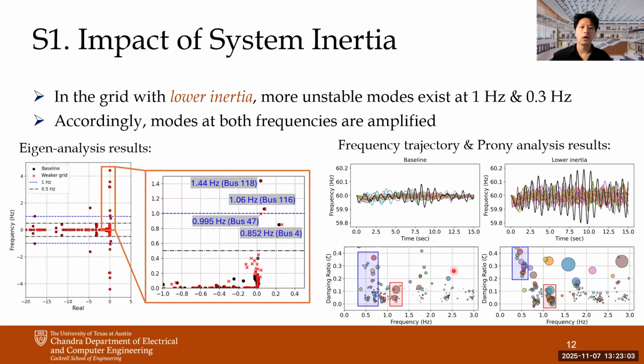Then we move to how the various factors can affect this kind of oscillation. And the first factor will be the system inertia. Basically, if the system has a lower inertia, there will be larger oscillations. But we are trying to analyze this amplification of the oscillations in a more systematic way. So we have conducted the eigenanalysis on the grid system, as you can see from the left figure. In the baseline system, you can see from the black points that there are some unstable modes around 1 Hz, as well as at the lower frequency around 0.4 Hz.